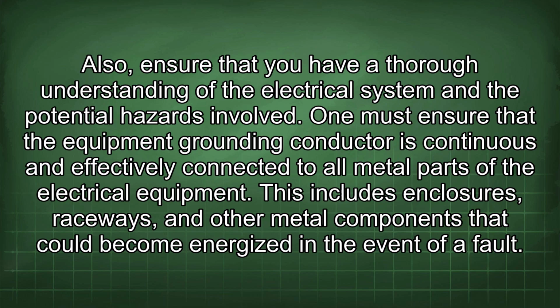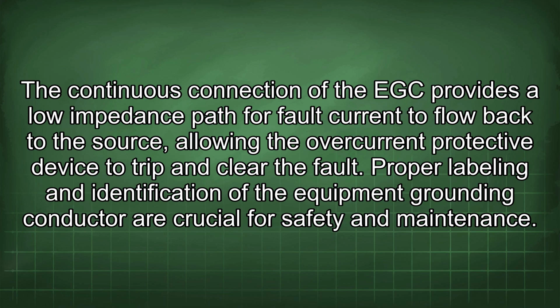One must ensure that the equipment grounding conductor is continuous and effectively connected to all metal parts of the electrical equipment. This includes enclosures, raceways, and other metal components that could become energized in the event of a fault. The continuous connection of the EGC provides a low impedance path for fault current to flow back to the source, allowing the overcurrent protective device to trip and clear the fault.